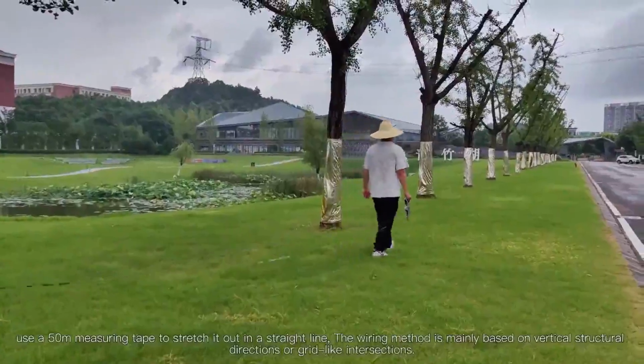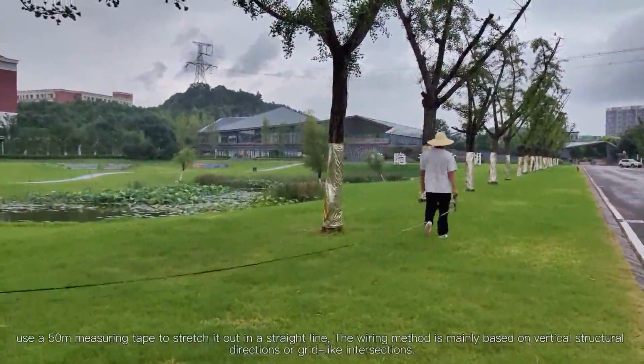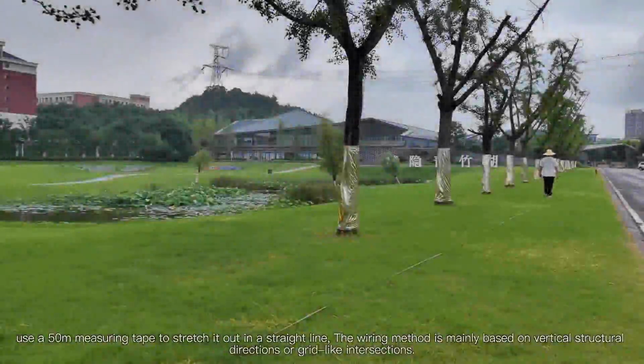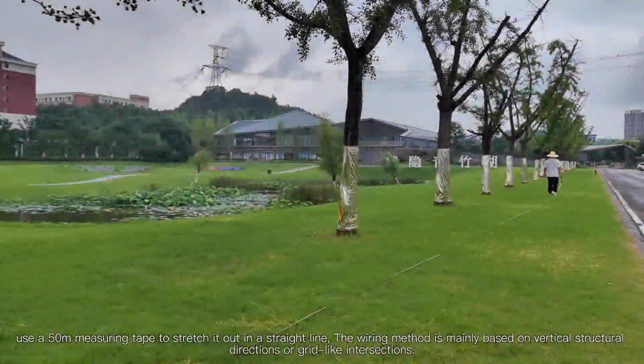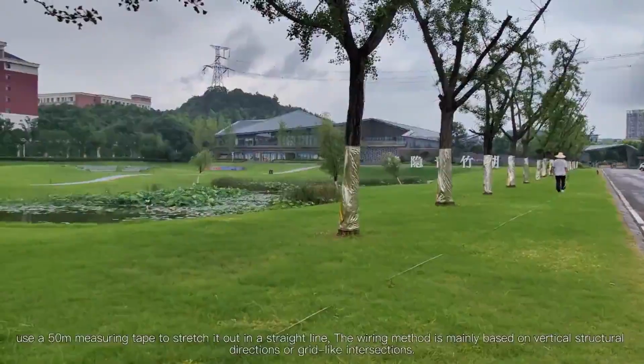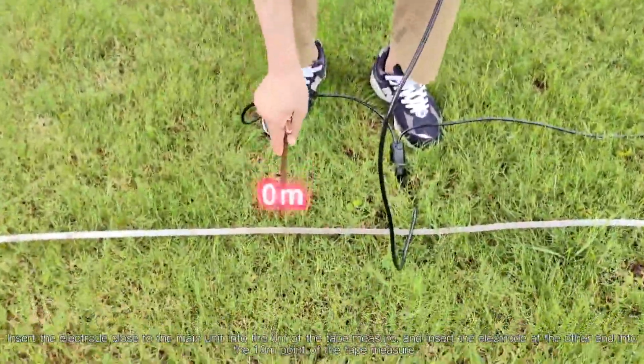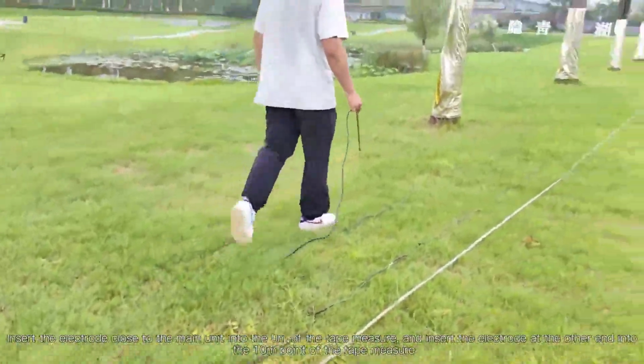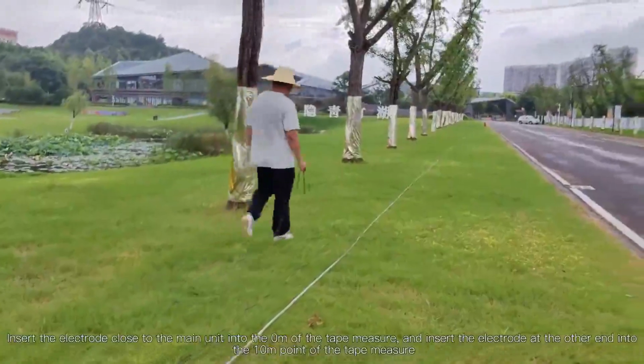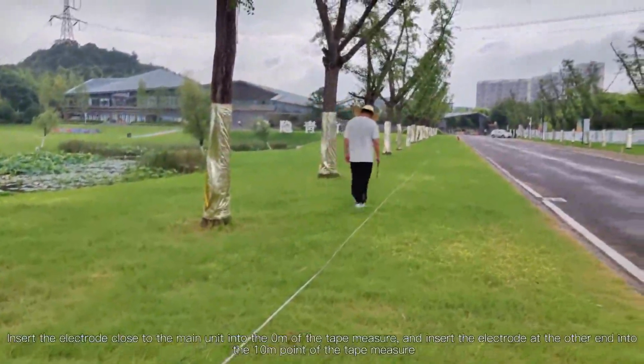Use a 50 meters measuring tape to stretch it out in a straight line. The wiring method is mainly based on vertical structural directions or grid-like intersections. Insert the electrode close to the main unit into the 0 meters of the tape measure, and insert the electrode at the other end into the 10 meters point of the tape measure.